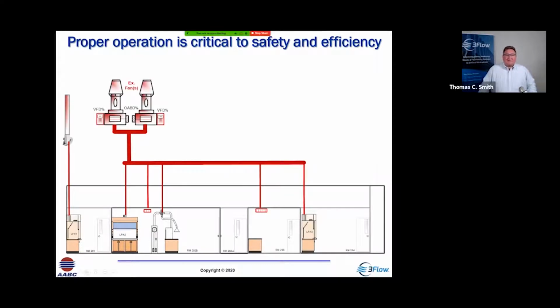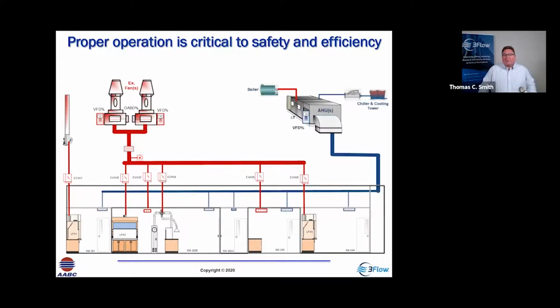And so we can have a single hood, single fan, or a manifolded exhaust system. And let's add some ability to modulate flow or to distribute the flow properly. So we have an exhaust system that enables us to achieve the appropriate flow through each of the devices. But because we're exhausting air out of the building, we have to supply air back to the building. And so we also have to distribute that flow properly.